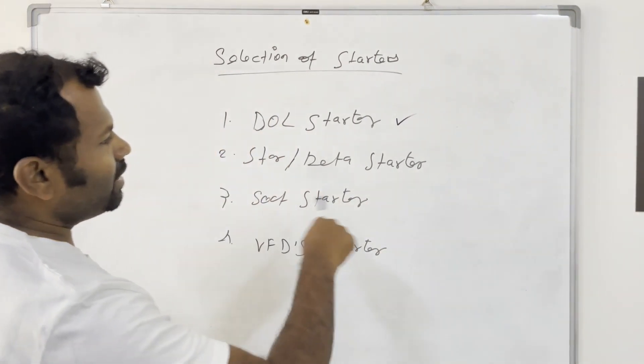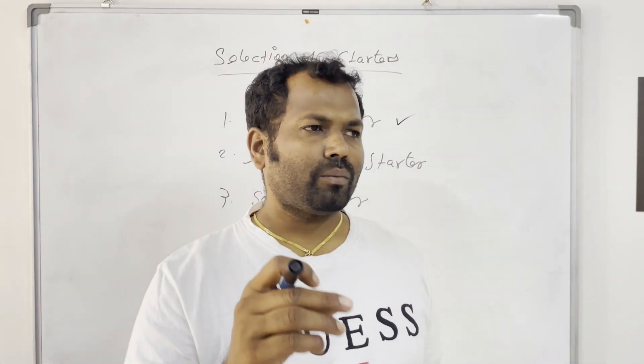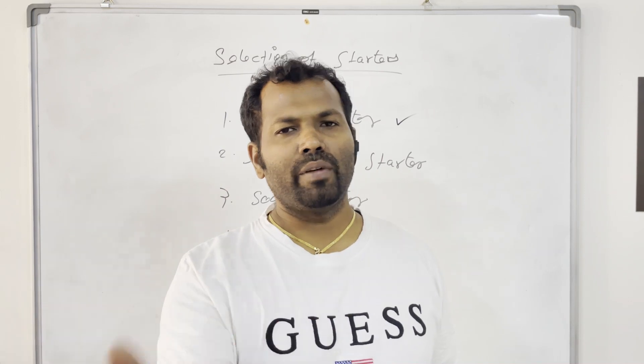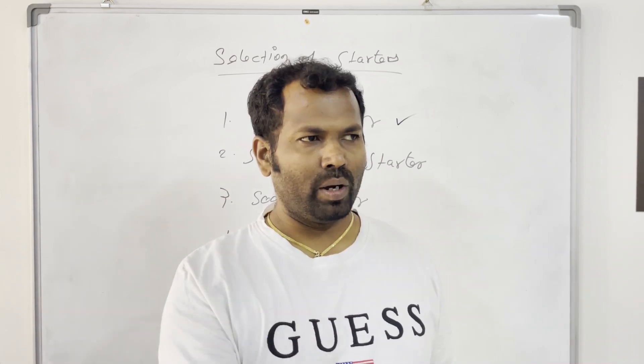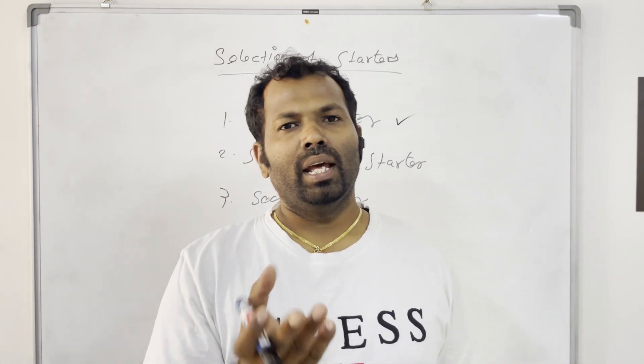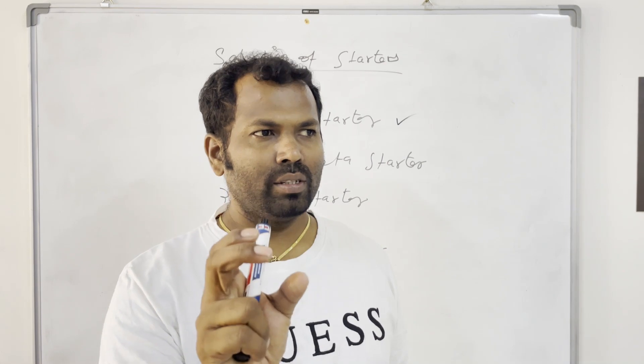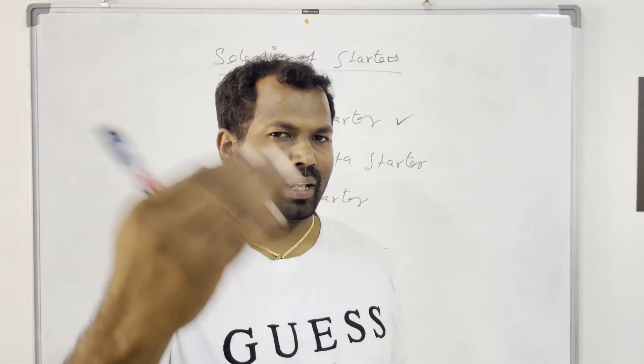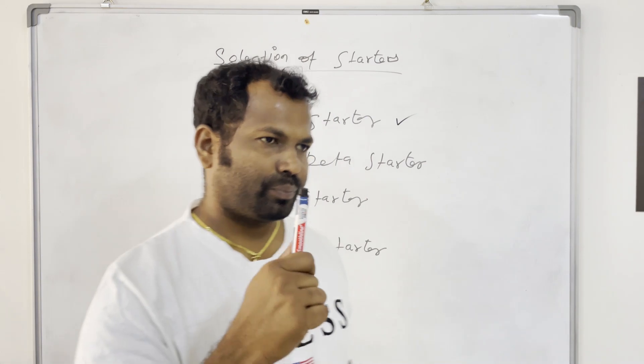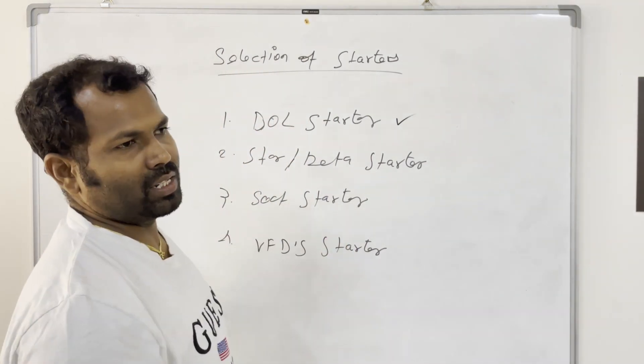Next, the Star-Delta starter — if your motor is a little bigger, like more than 5.5 kW or 7.5 kW, and you don't want speed control, you can use this Star-Delta starter to reduce starting current and starting torque.